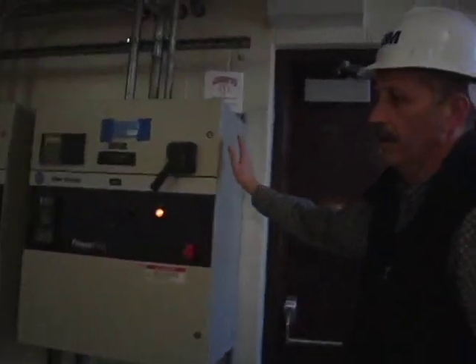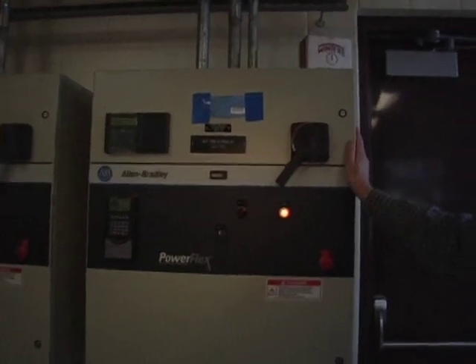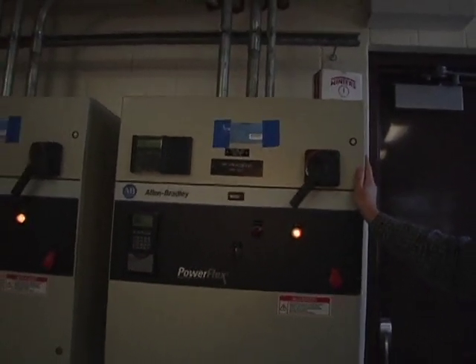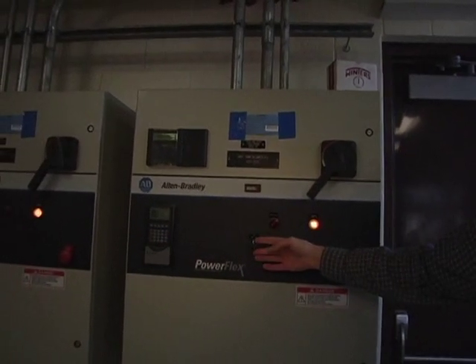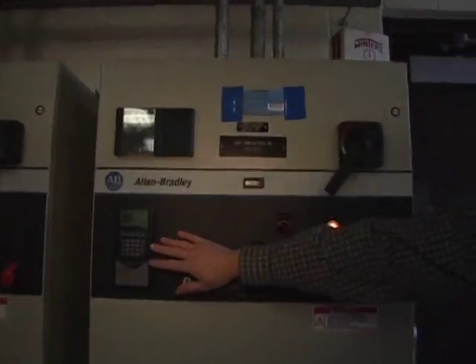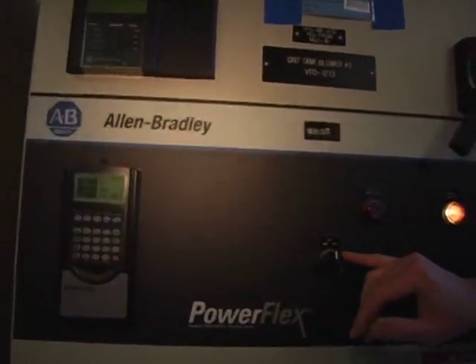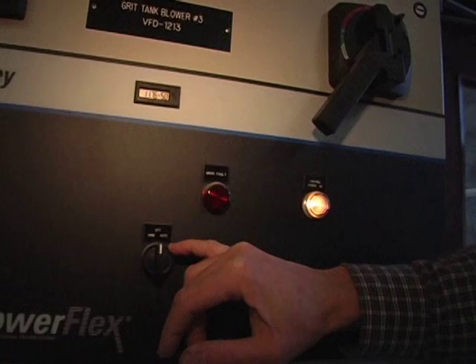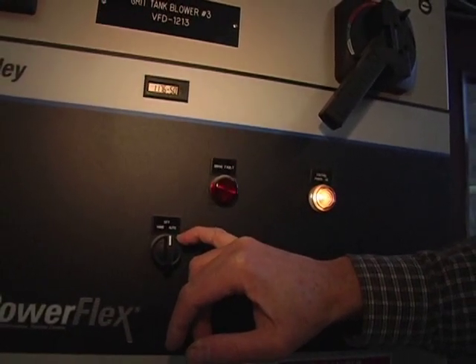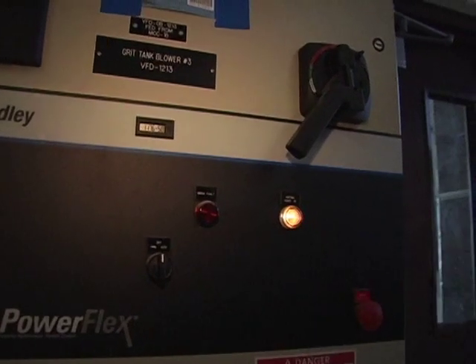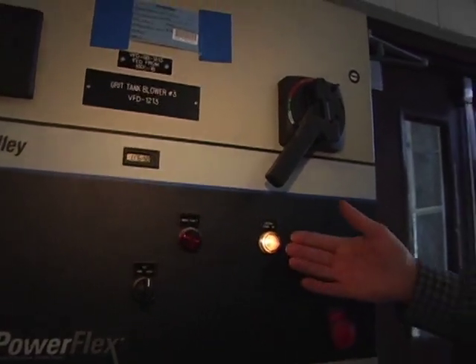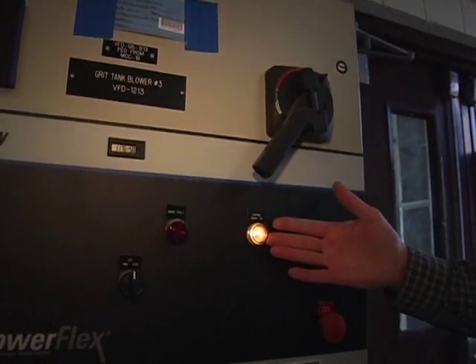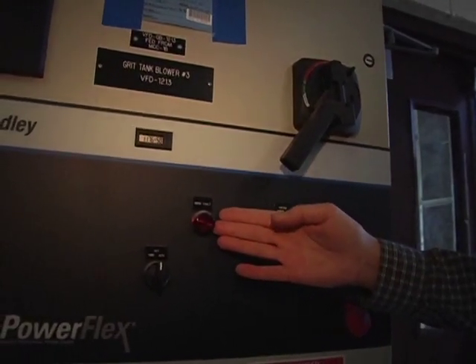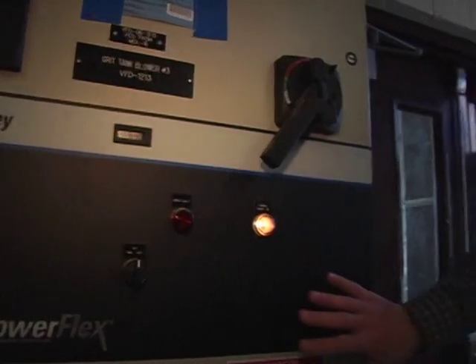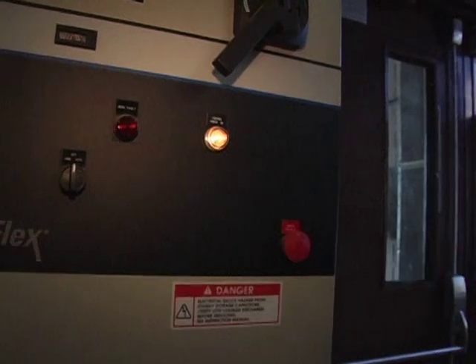Going further around the room, we've got the VFDs for the blowers. These are for the grit chamber blowers, one VFD per blower. They can be run in either hand, being the local operation here, where you can adjust the speed using the keypad, or if you go to automatic, then the control for the blower goes to the SCADA system. So the operator can then adjust the speed of the blower through SCADA. When the system is on, you've got a control power lamp on. If the system goes into a fault, you'll get a drive fault alarm, and you also have a disable button or an emergency stop button for the system.